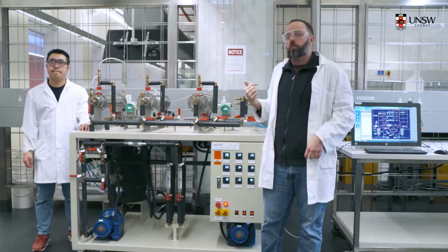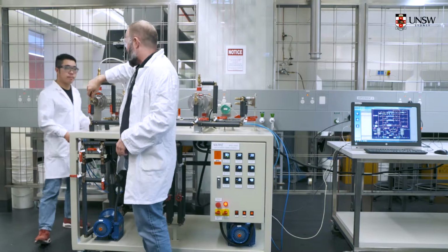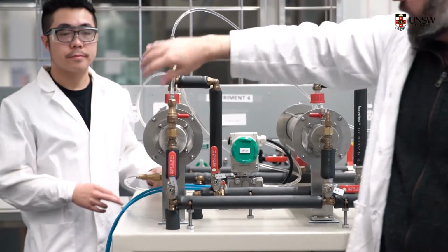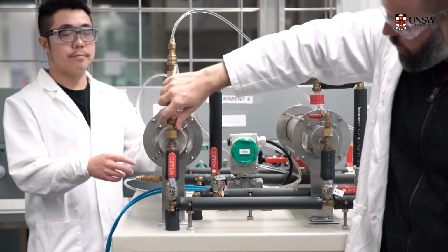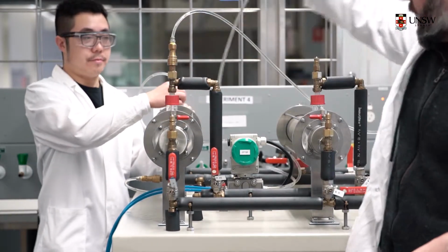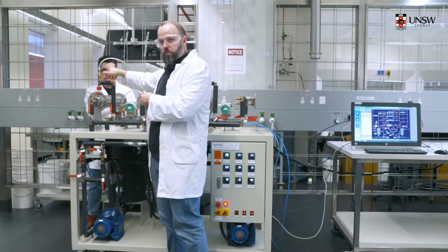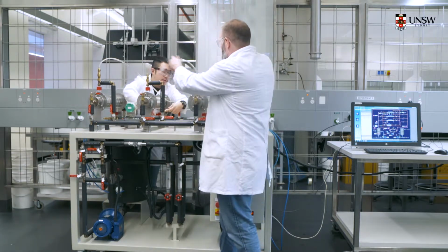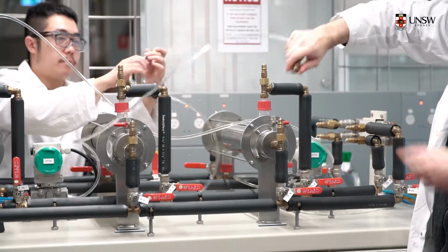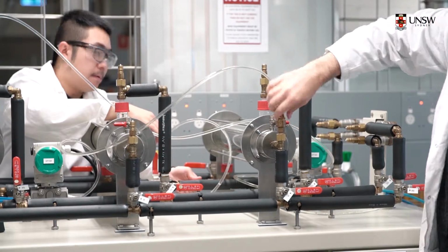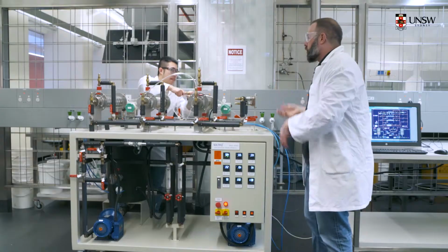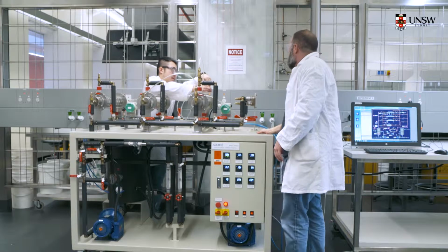To measure pressure drop in the heat exchanger, we use these connection lines. Basically, there's a set for the cold water and a set for the hot water. To change these out, it's not too difficult, but it's definitely worth taking a look at through this demonstration. Each one of these connectors, you slip up the outer sheath, and it pops right back out. Let's say we're done measuring the pressure drop here, and we want to measure the pressure drop on the concentric heat exchanger. We move the lines over, pull back the outer sheath, make sure it's all the way in, and then let it go, and check to make sure that it's snug and there are no leaks. It's the same thing on both the inlets and the outlets. Pretty straightforward, but if you have not seen this before, it might look completely foreign to you.